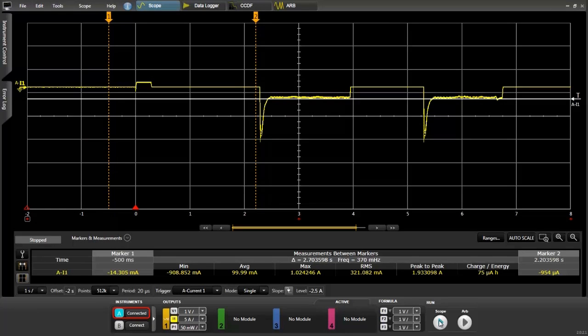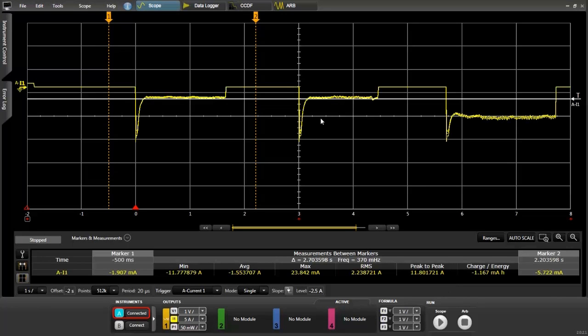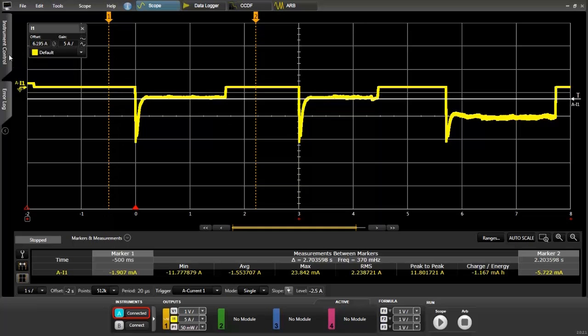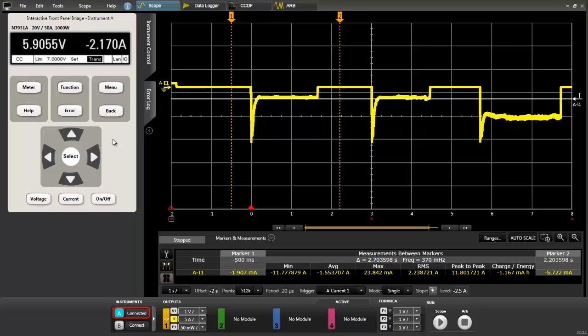We're now back in scope mode. I've set everything up so that we can properly capture the current being drawn from the battery. All we need to do is click play on the scope again. The pre-trigger is filling. We click play on the ARB and now the waveform that we created is being pulled from the battery. And we can see that the data is being pulled down at this point. You can see the waveform on the screen. It's the exact same waveform that we captured from the electronic vehicle but it's the inverse because it's being pulled from the battery. This is really a great feature because it's very simple to set up but it's a very complex task to do without these instruments and this software.